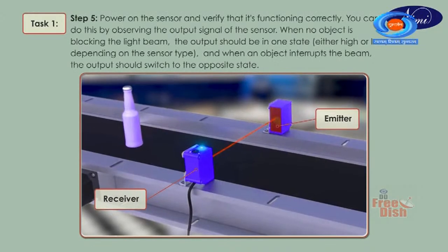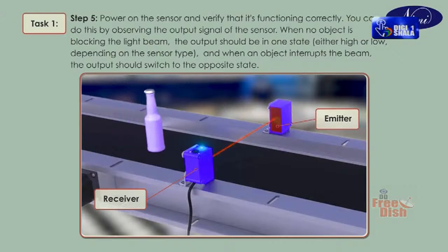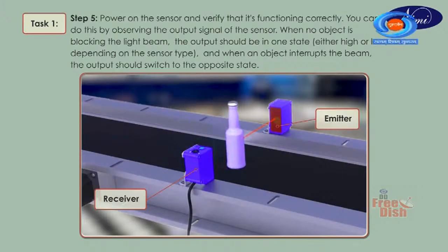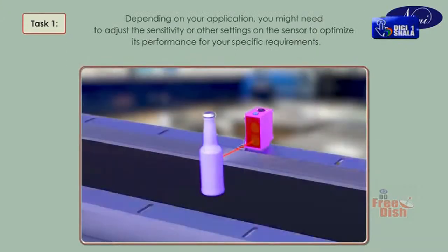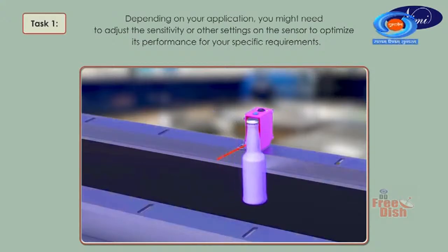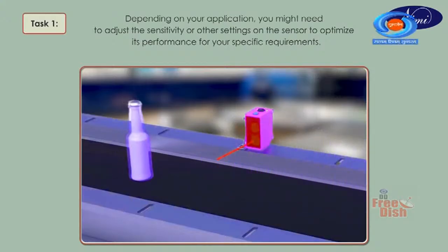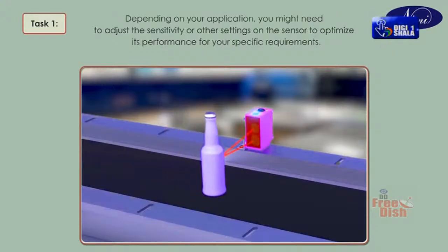Step 5. Power on the sensor and verify that it's functioning correctly. You can do this by observing the output signal of the sensor. When no object is blocking the light beam, the output should be in one state, either high or low, depending on the sensor type. And when an object interrupts the beam, the output should switch to the opposite state. Depending on your application, you might need to adjust the sensitivity or other settings on the sensor to optimize its performance for your specific requirements.